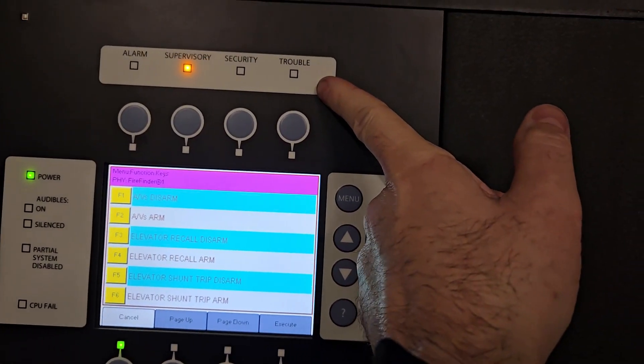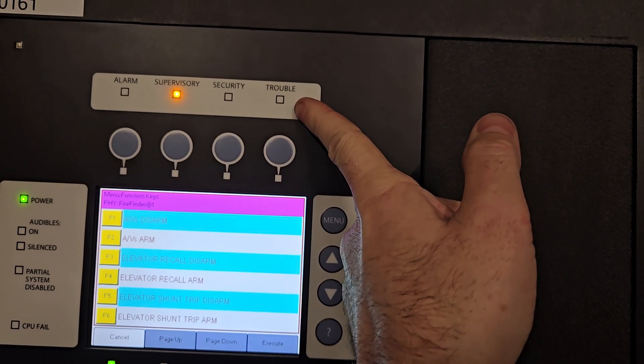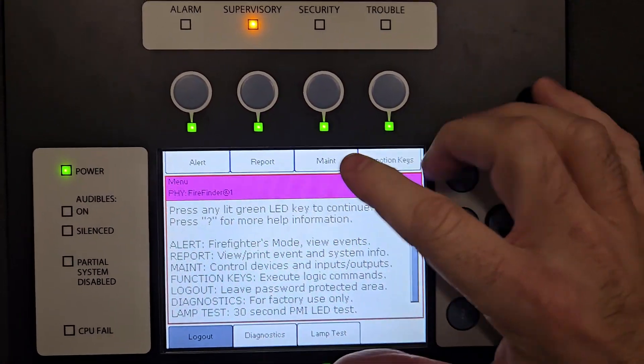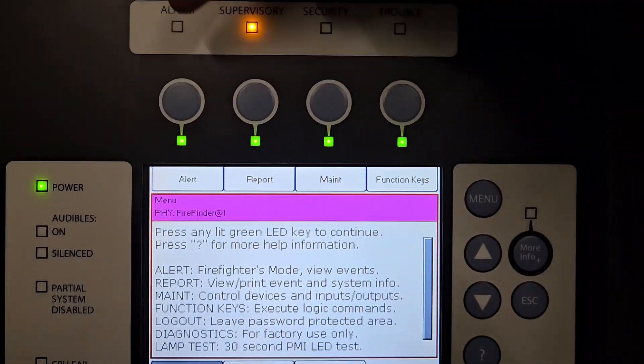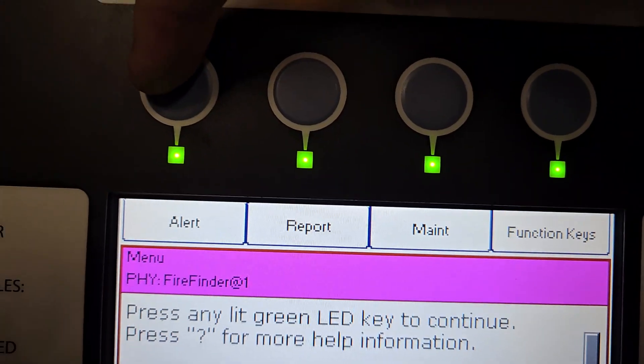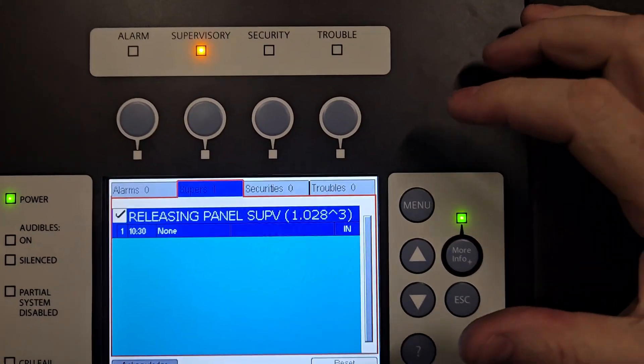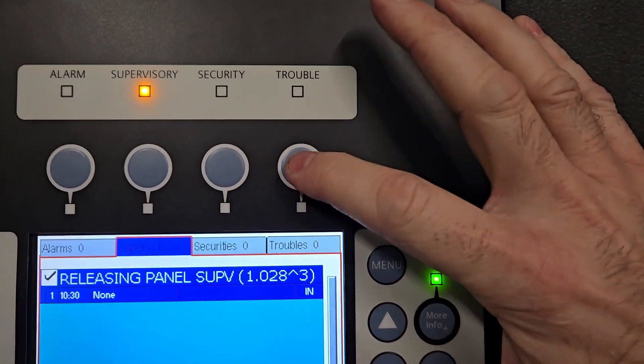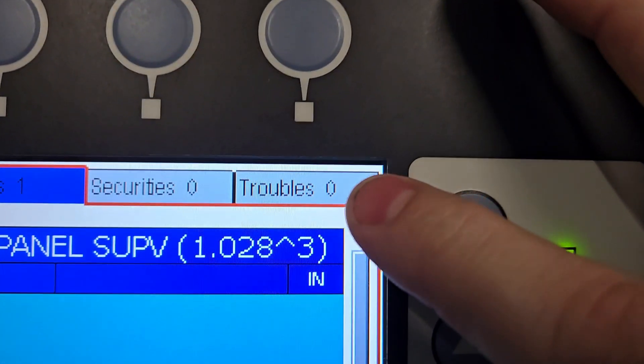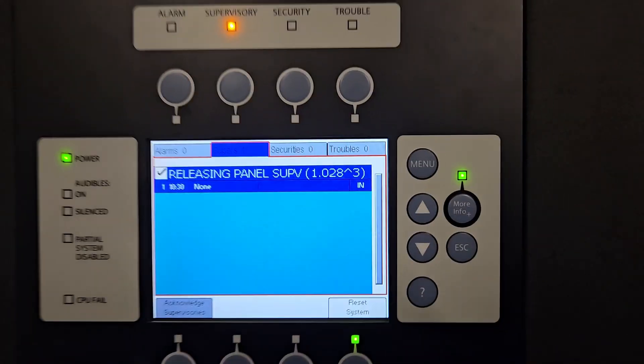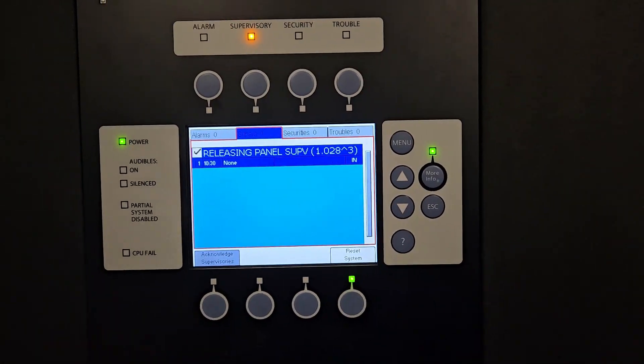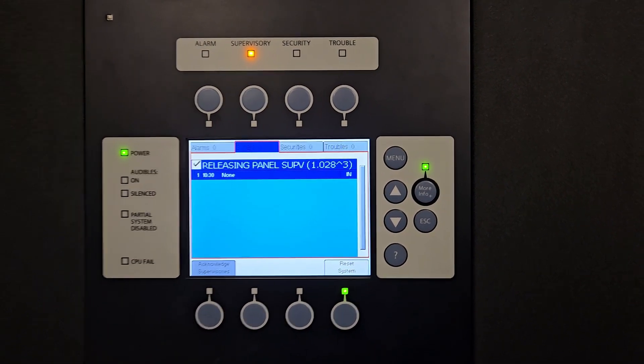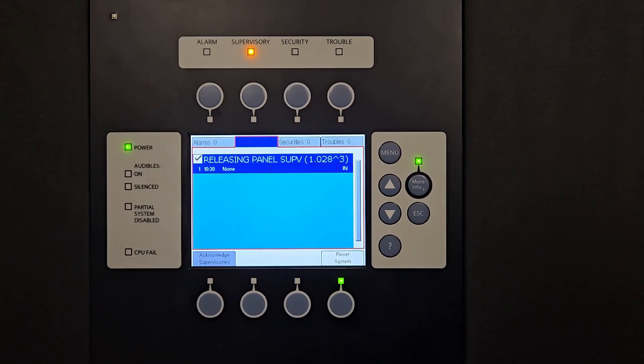You see up here my trouble cleared. Just to verify that, we're going to go out to the menu again and go to the left where it was alert. My trouble's gone — I can't even select it because I have no troubles and haven't disarmed anything. So now the audio-visual circuit is armed again. If I test any smoke detectors, pull stations, or anything like that, the horn strobes will activate and they will go off.